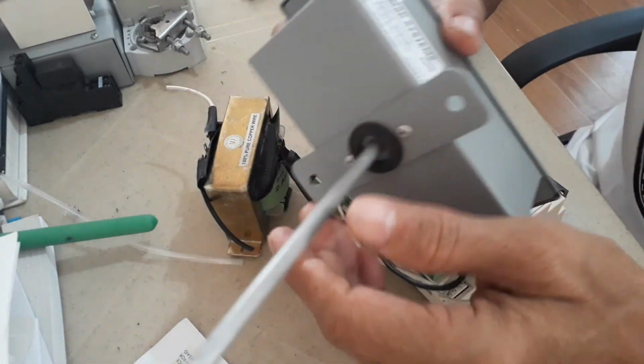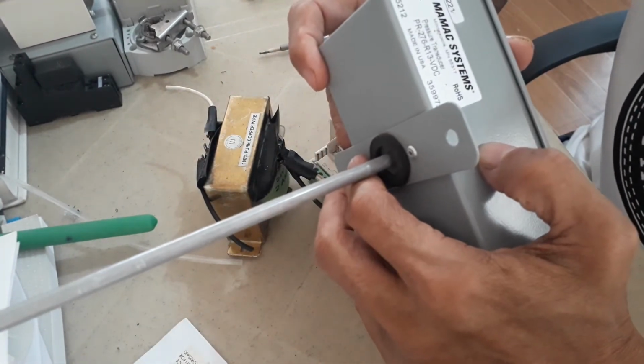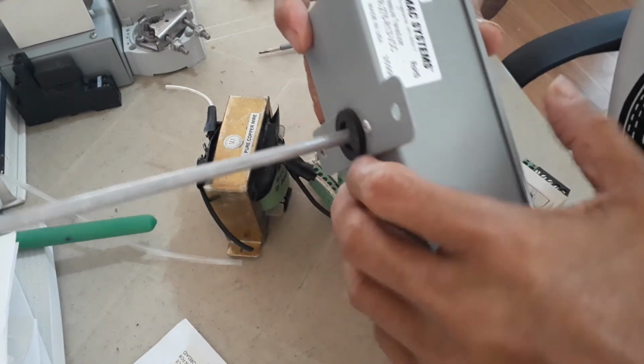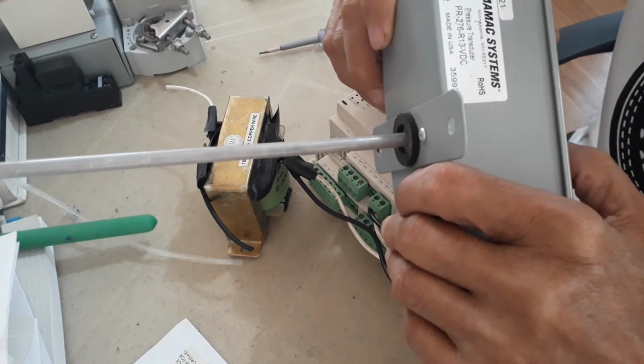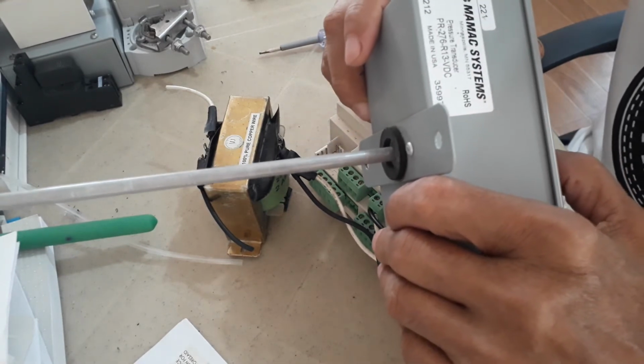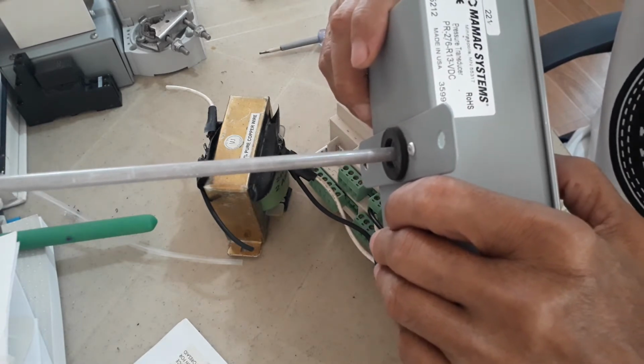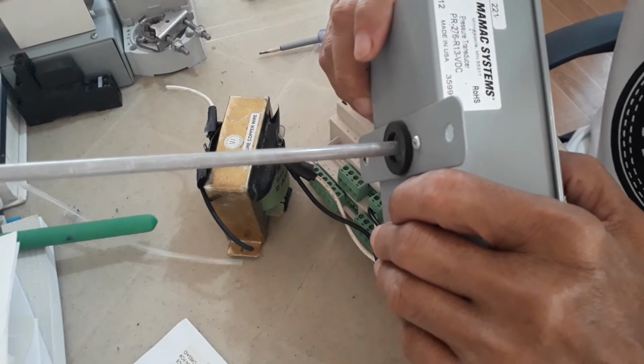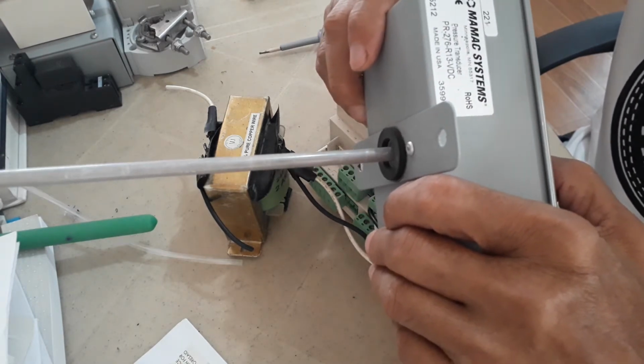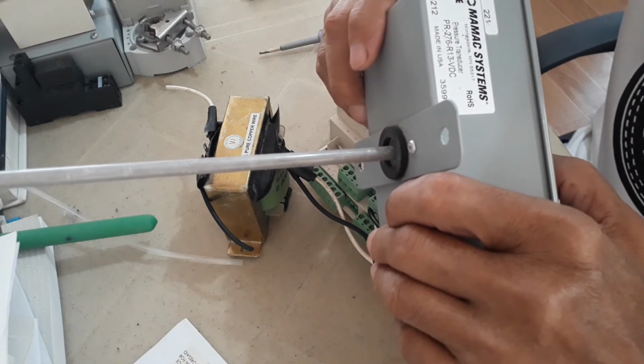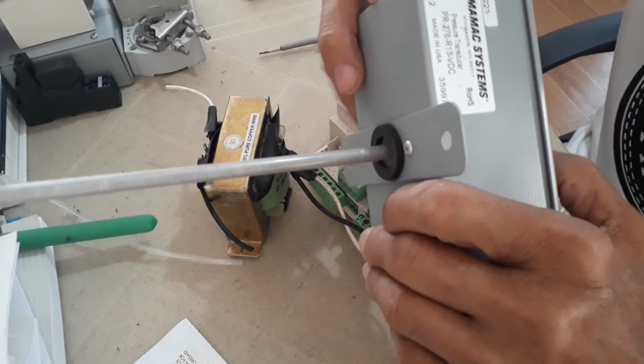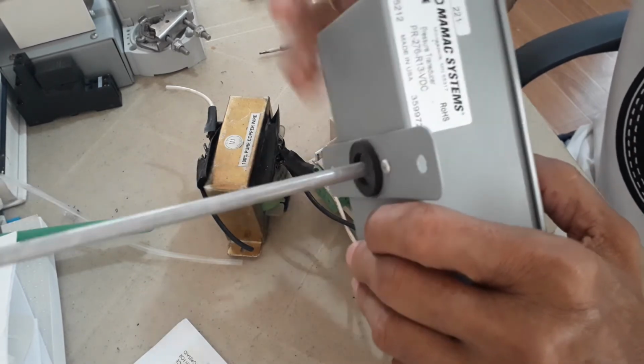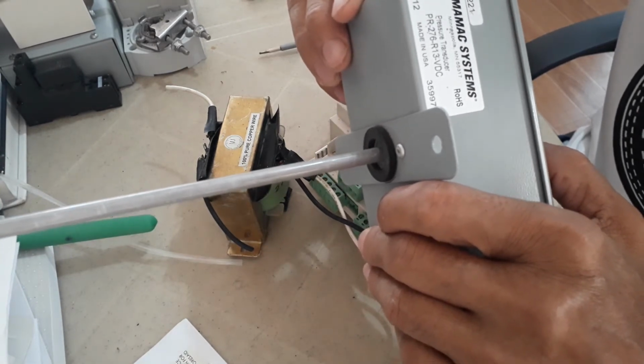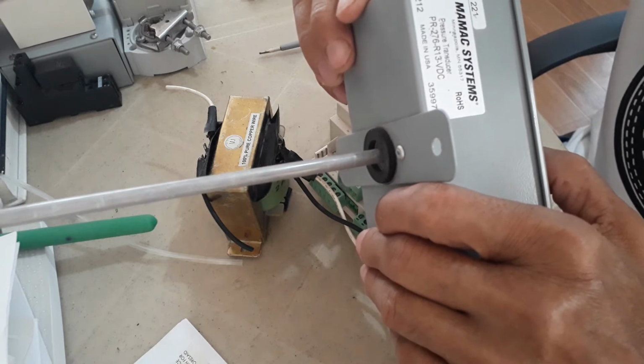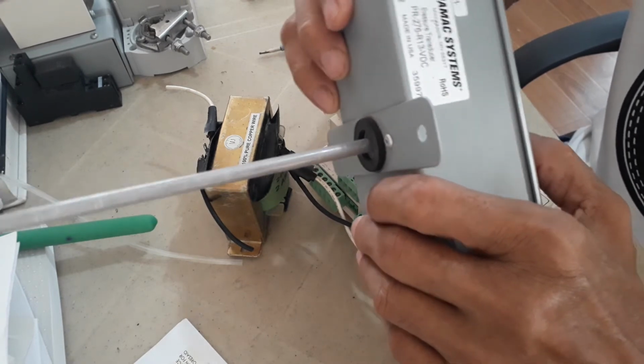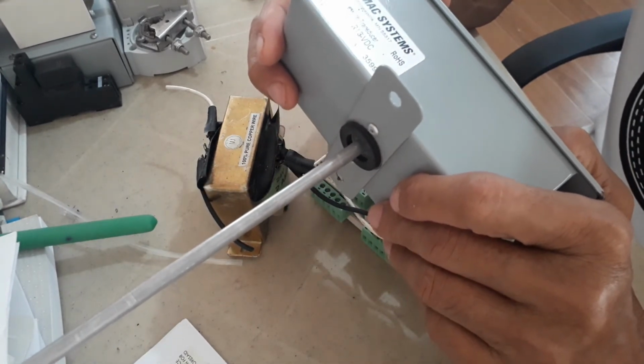Okay, now this one you can use. In my previous projects, we used this for sensing the pressure in a duct, especially if we are controlling the speed of the fan. Meaning, these air handling units are serving variable air volume boxes. So when the VAVs close, then there will be high pressure in the duct. Then this one will give that pressure reading in my control logic that I need to slow down my fan so it will not create high pressure in my duct, to prevent damage in the duct. So this is used for controlling the speed of the motor that drives the fan.